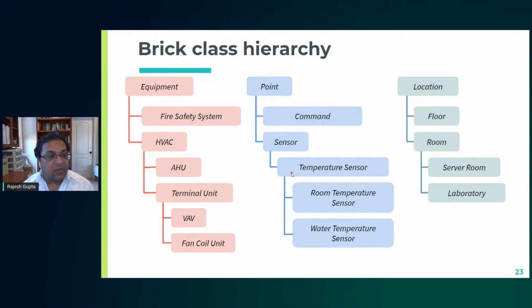So the obvious thing we did was we said, okay, let's take 3 types of things: equipment, control point, and location, and create each one of them as a class hierarchy. So equipment can be a subtype of fire safety, it can be a subtype of HVAC, which can have a subtype of air handling unit, AHU. It could have a terminal unit. Terminal unit means the unit that is serving a zone, and that could be a variable air volume box, or it could be a fan coil unit, whatever. Okay, same thing with control points. You could have a command, you can have sensing information, you can have a sensor of one kind or the other. A location could be geometric, or it could be logical, for example, a floor, a room, a server room, or a laboratory. So that builds relationships between these different objects of the same class hierarchy.